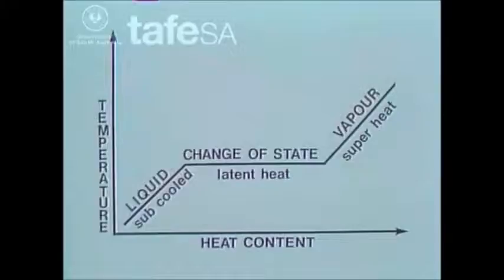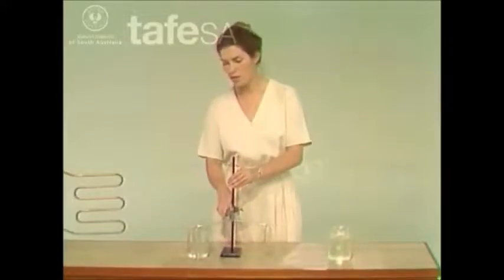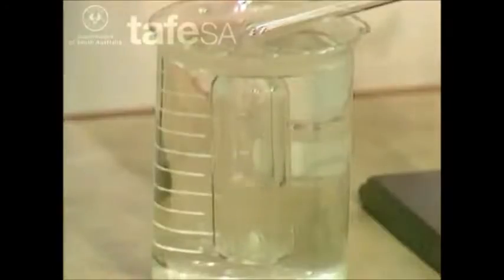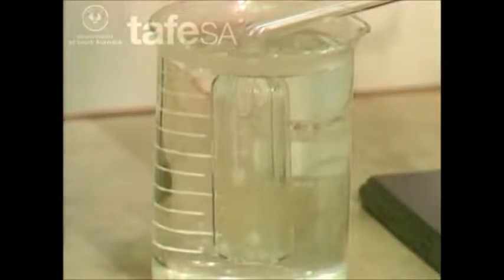It only takes a slight change in either the pressure or heat content of the refrigerant to change the saturation temperature. If I heat the refrigerant with this hot water, the extra heat makes it boil, and the pressure in the tubing will rise. The increased pressure raises the boiling temperature, and when that's the same as the water, a new saturation point is reached.